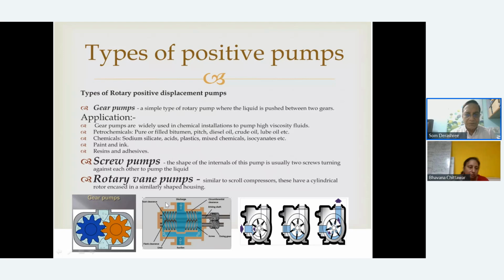We have screw pumps, which is the second picture at the bottom. You would find there are two screws, and the screws rotate, pushing the material forward. And there you have a rotary vane pump, also known as a peripheral pump, where the fluid enters from one side, and then these rotating blades take it forward and push it. This is a slightly eccentric opening, so the material gets pushed out as it moves forward along this circular path.